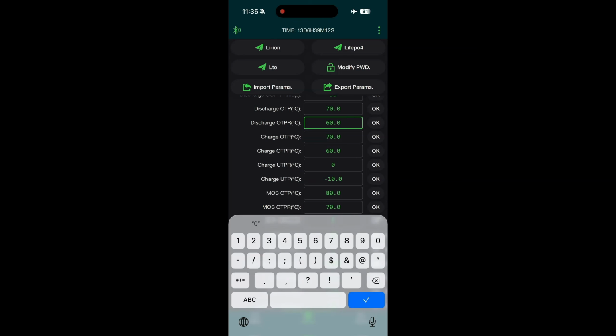And again, this is ambient temperature, so it depends on what you're doing there. Same thing with the next two settings. Charge OTP is Charge Over Temperature Protect, and then the next one down from there is OTPR, which is when it is going to reset. So if you've got both of these set to 70 as the protect and then 60 as the reset, anytime it goes up to 70 degrees, it'll stop allowing charge or discharge, and then as soon as it gets under 60 degrees, it will allow the charge or the discharge to continue.